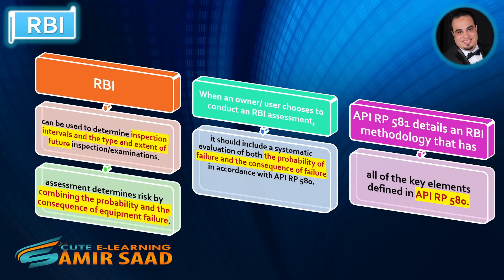Risk-based inspection (RBI) can be used to determine inspection intervals and the type and extent of future inspection examinations. An RBI assessment determines risk by combining the probability and the consequence of equipment failure. When an owner-user chooses to conduct an RBI assessment, it should include a systematic evaluation of both the probability of failure and the consequence of failure in accordance with API RP 580. API RP 581 details an RBI methodology that has all of the key elements defined in API RP 580.